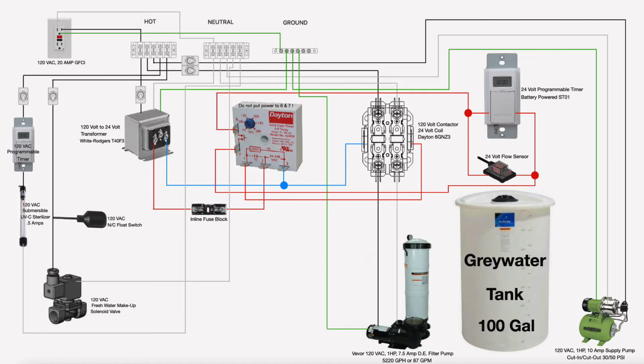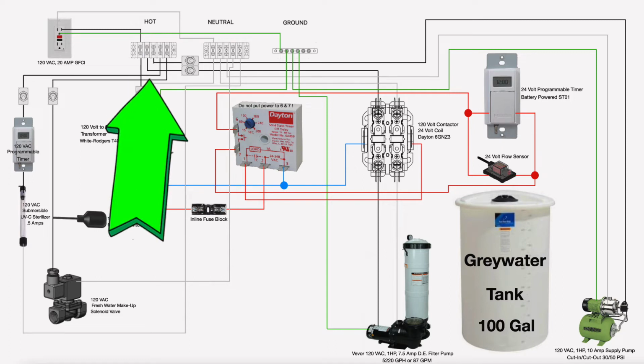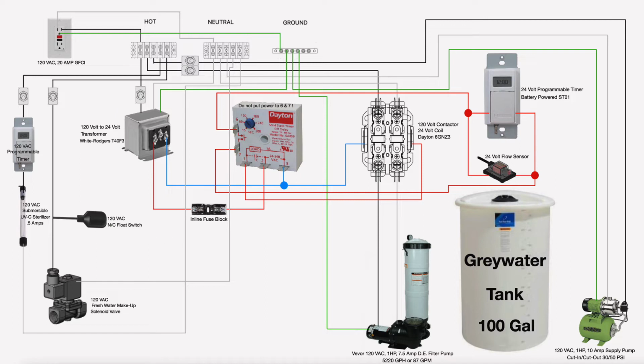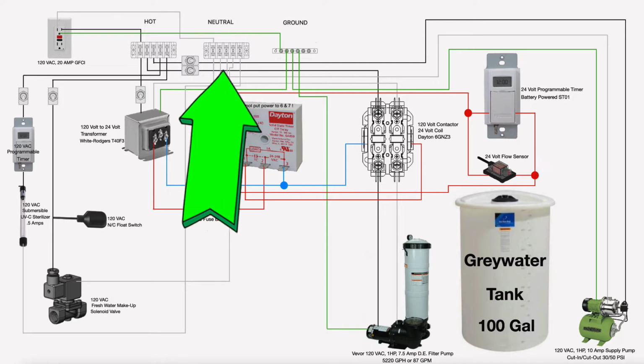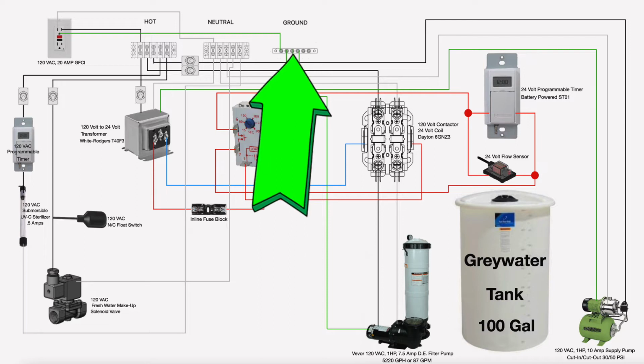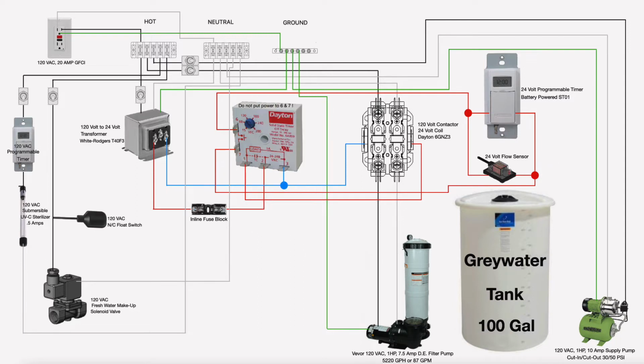So you can see across the top, we have our hot 120 volt screw terminal block, our neutral terminal block, and our ground terminal bar or terminal block. All the black wires are 120 volt hot wires. All the white wires on this schematic are your 120 volt neutrals. All your green wires are your ground wires. All your red wires are 24 volt AC hot wires. All your blue wires are your 24 volt AC neutral or common wires.